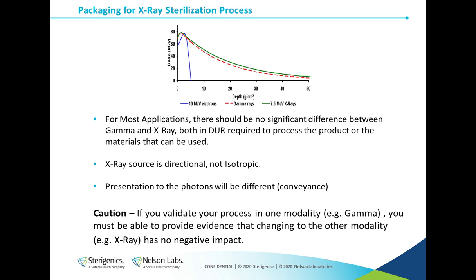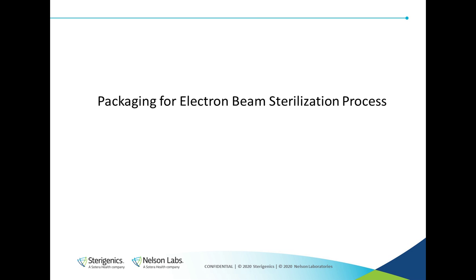For most applications, there should be little or no significant differences in gamma and X-ray packaging or material effects. There is a caution, however, and that is if you validate your process in one modality, like gamma, you must be able to provide evidence that changing to a new modality, like X-ray, has no negative impact on your sterilization packaging or product.